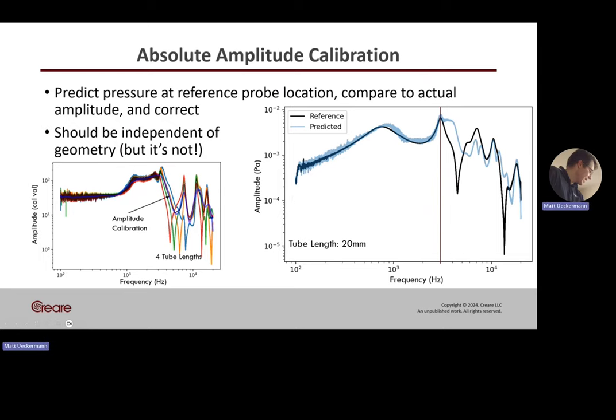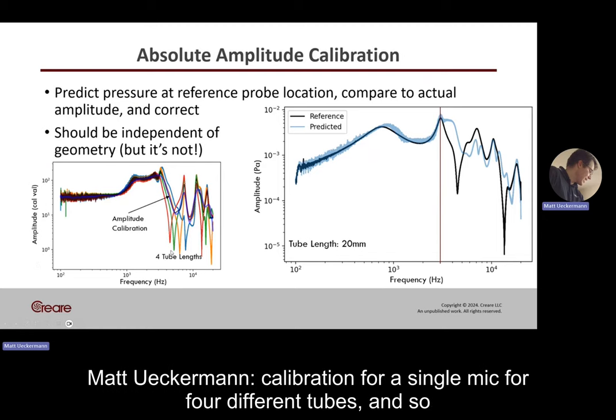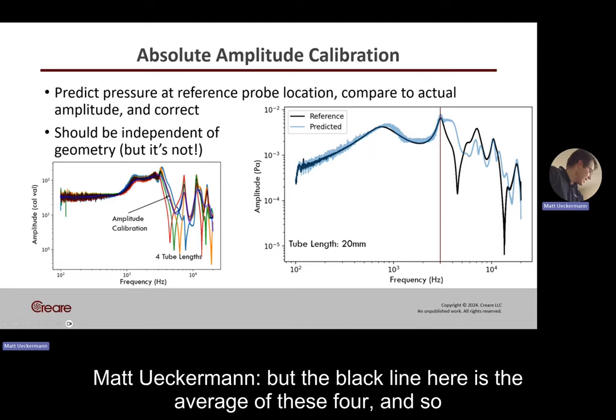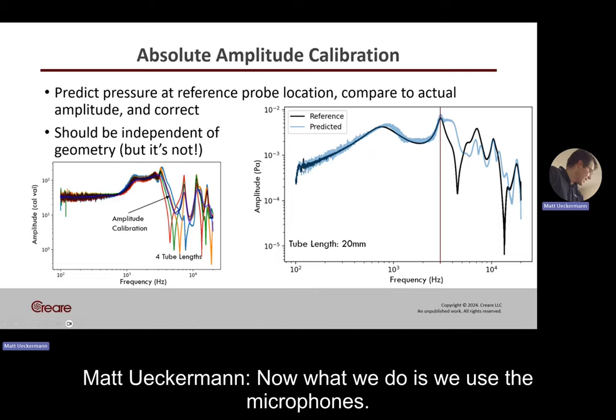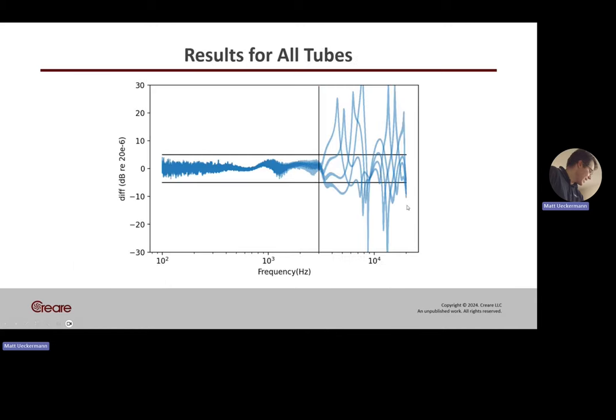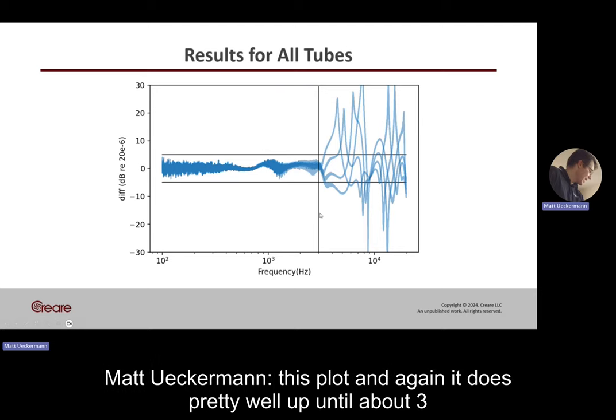The next step is the amplitude calibration. This plot shows frequency versus the amplitude calibration for a single mic across four different tubes. Ideally those colored lines would all be in the same place, but the black line — the average of the four — is the actual calibration used. As a sanity check, we use the microphones measured in order to predict the reference microphone, and that does very well up to about three kilohertz. Looking at the difference between pressures on a dB scale across all the different cavities, it also does pretty well up until about three kilohertz.